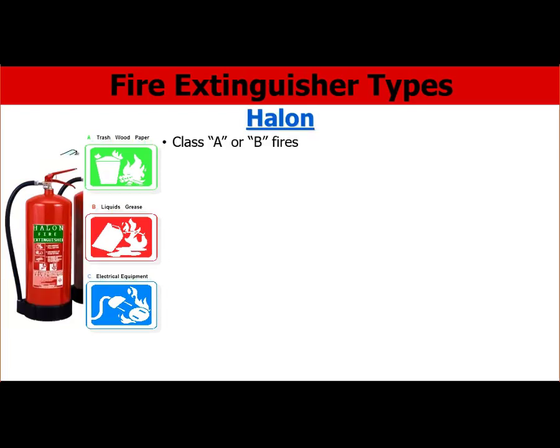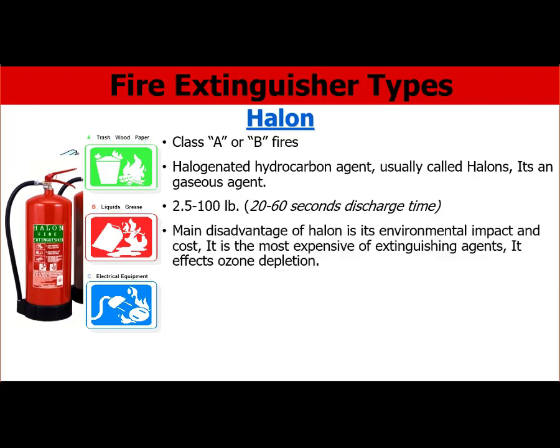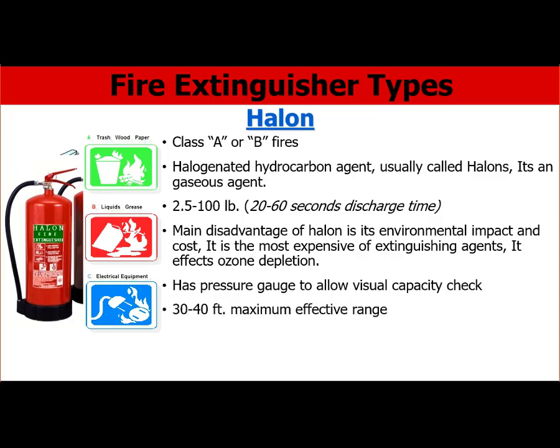The last type is Halon, used for Class A and Class B fires. It uses a halogenated hydrocarbon agent — it's a gaseous agent. It usually comes with 2.5 to 100 lbs and takes 20 to 60 seconds of discharge time. The main disadvantages of Halon are its environmental impact and high cost — it is the most expensive extinguishing agent and affects ozone depletion, so it is banned by most countries and used only under very specific conditions. It has a pressure gauge and an effective range of approximately 10 to 14 feet. It also extinguishes by smothering, like DCP, CO2, and foam.